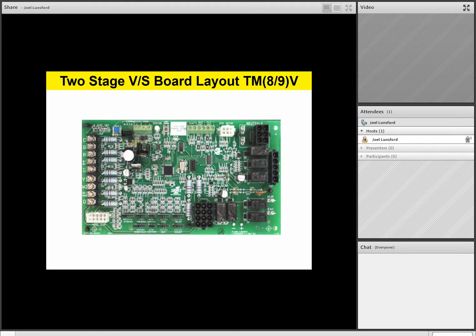A variable speed product, with a V, will have a control board like what we're looking at here. Please follow along as we talk about all those components. Again, the variable speed boards will have jumpers on them that we can select airflow with, and we'll talk about that in just a little bit. So starting on the left-hand side of our two-stage variable speed control board, again, examples would be a TM8 or TM9V product.